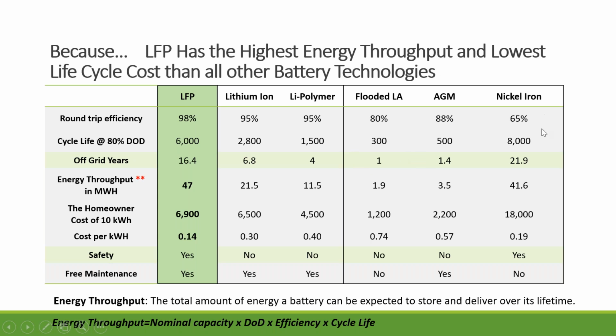Nickel iron is pretty good, at 8,000 cycles. In off-grid years, if you count 1 cycle per day, that's how many years you can expect the battery to last. With LFP, you can expect around 16 years. Nickel iron is the best, at 22 years. But with flooded AGM, if you do 80% DOD, you're really talking about a year or two if you do that every day.